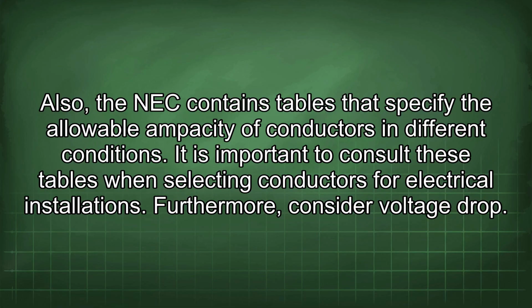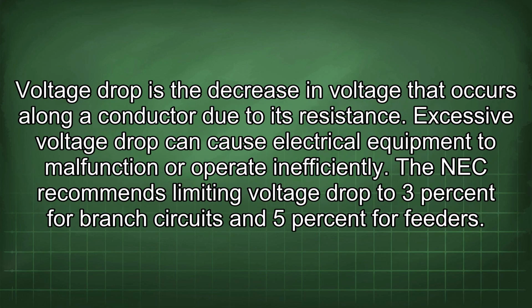Furthermore, consider voltage drop. Voltage drop is a decrease in voltage that occurs along a conductor due to its resistance. Excessive voltage drop can cause electrical equipment to malfunction or operate inefficiently. The NEC recommends limiting voltage drop to 3% for branch circuits and 5% for feeders.